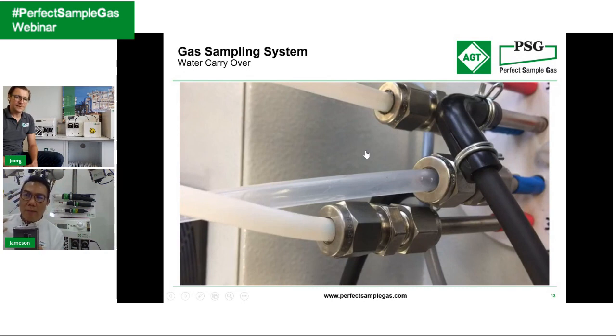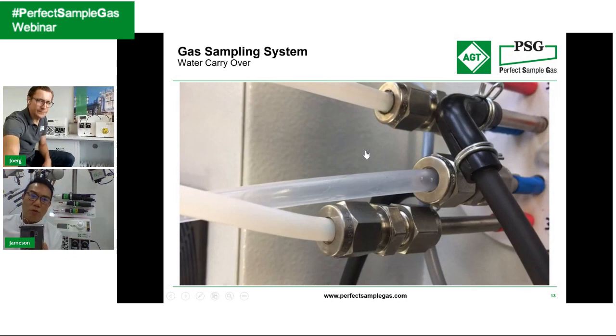So the gas cooler, why do people buy it so expensive? The gas cooler is to remove the heat from the hot gas in the shortest time, to chill it down to 3 degrees, to squash out the water. So this is the first mistake, allowing condensation just before entering the gas cooler. Number two, the possibility is the sample pump. Many people have oversized the sample pump without understanding the capacity the gas cooler can handle. This is another possible reason. Therefore, it is important to be aware, depending on the gas cooler, whether they are connected in series or in parallel. This is very important to prevent all this water carrying over.